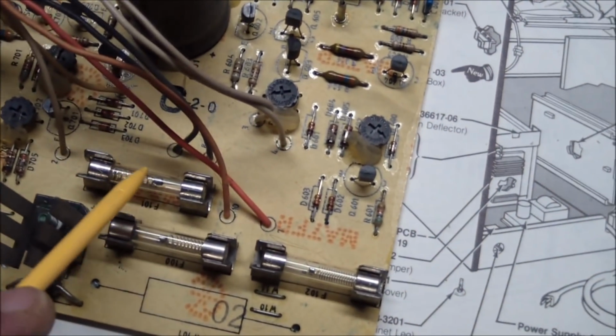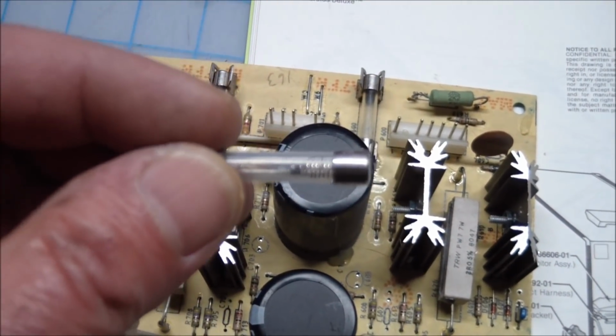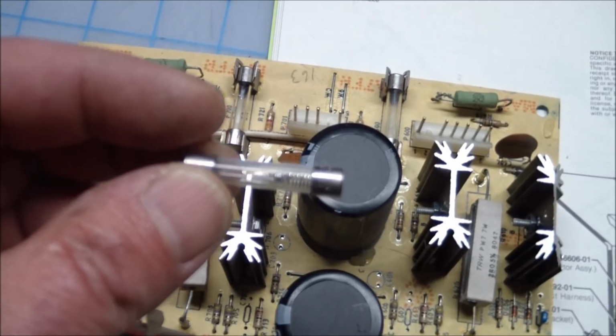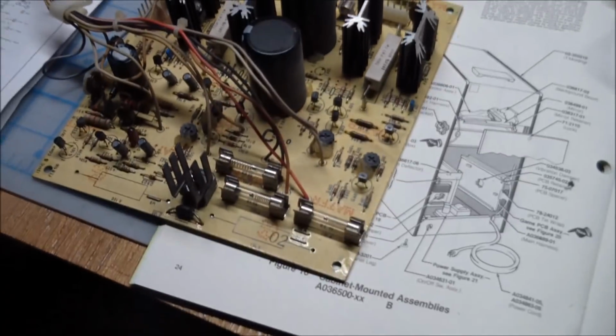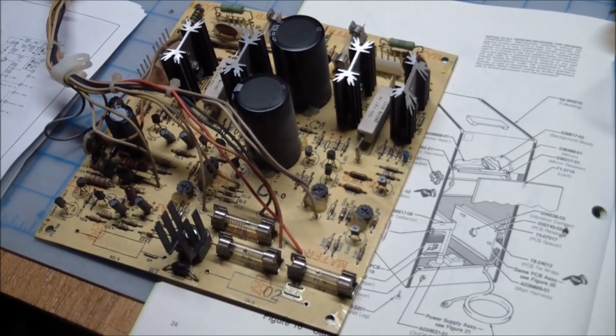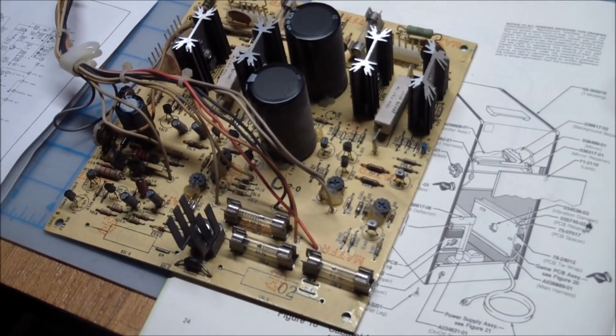And this one was open. You couldn't really see it. It's not going to focus on it. But, looking at it, it looked fine. Nothing seemed to be broken, no burn marks in it or whatever. But do not base your judgment of a fuse's functionality plainly on visuals.